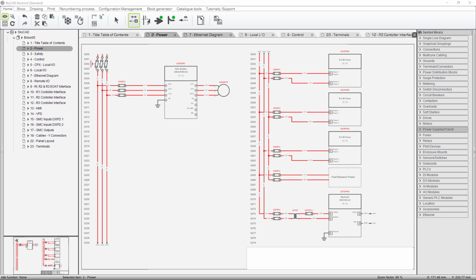Okay, 3 phase. Now in our system here, we've only got 1 3-phase load. That 1 3-phase load is the variable frequency drive. You'll see that I have 3 conductors coming through fuses to that variable frequency drive. Now, I always start in the upper left-hand corner and I bring in my 3-phase power, because remember, that 3-phase power drops from the ceiling, from the bus and the plant, down to your panel. Comes through an opening, and the first place it goes is the disconnect. Goes to the top terminals on your fusible disconnect or your circuit breaker.